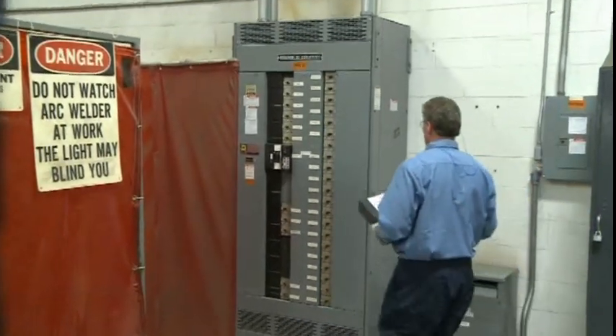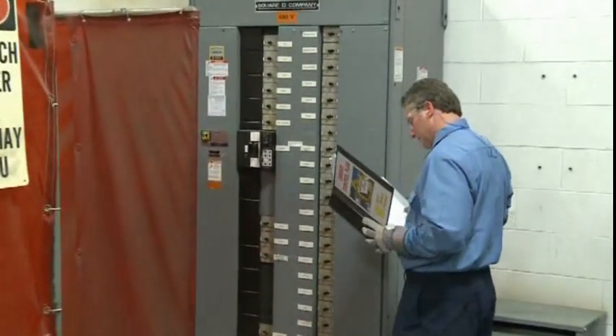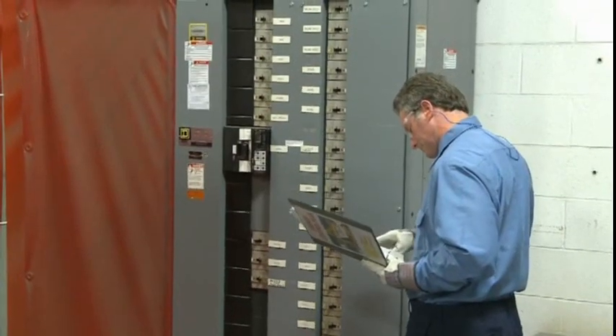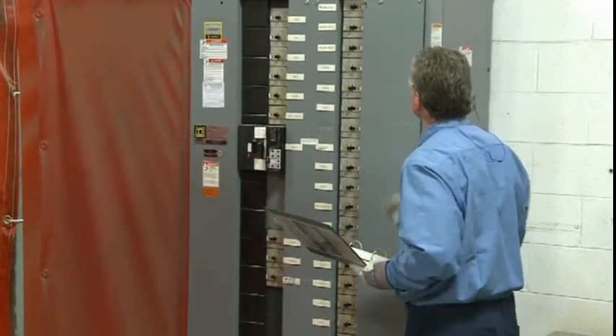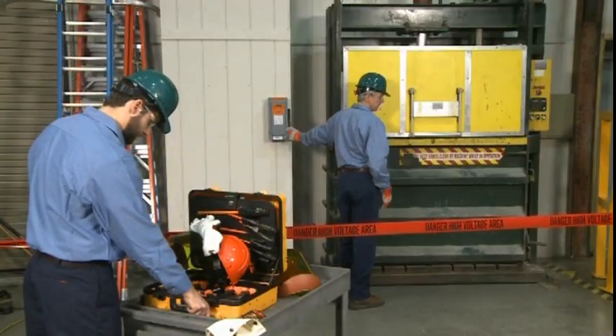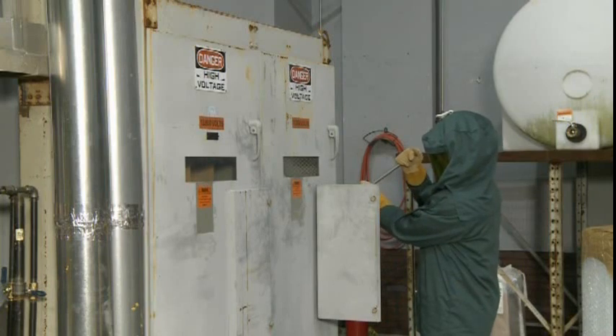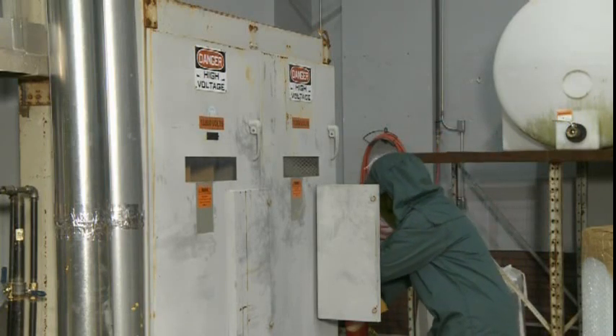To create an electrically safe work condition, first determine all possible sources of electrical supply to the equipment. Next, disconnect any active loads, then open the disconnecting device for each source.